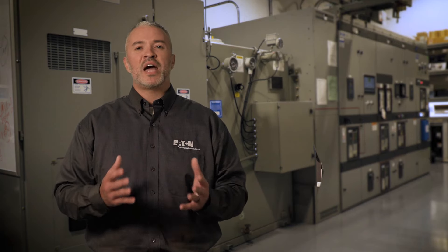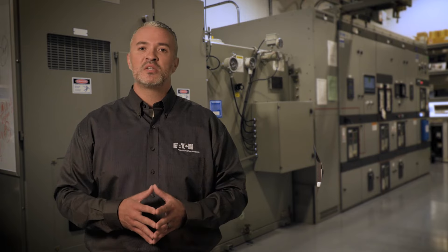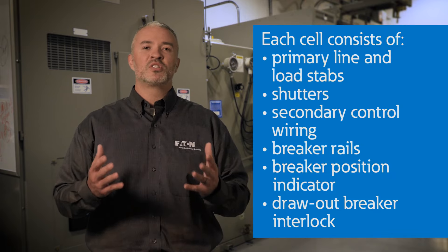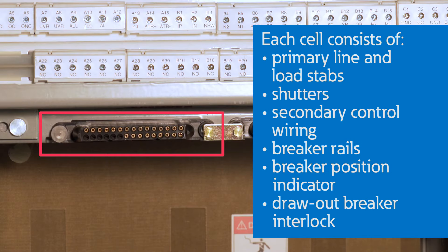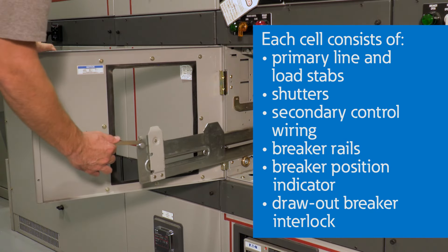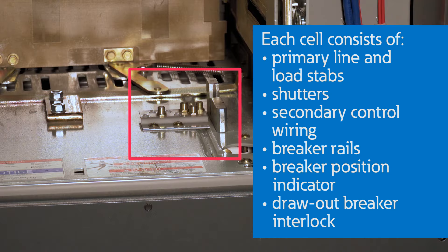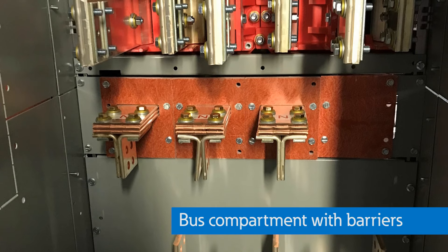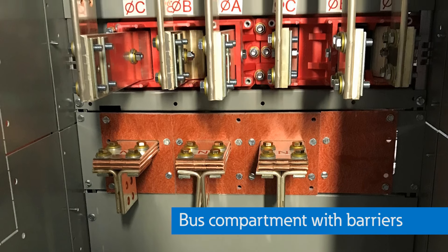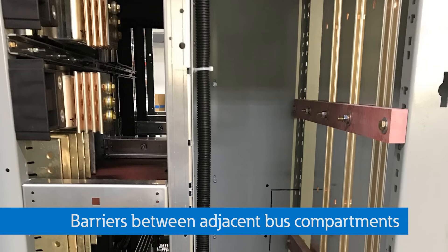For example, should a catastrophic fault occur on a circuit breaker, the internal barriers within the switchgear will reduce the likelihood of damage to adjacent breakers, internal bus, and the structure. Each compartment or cell generally consists of primary line and load stabs, shutters, secondary control wiring, breaker rails, breaker position indicator, and a draw-out breaker interlock which prevents the insertion of circuit breakers with incorrect frame size and interrupting ratings. Behind the circuit breaker compartment is the bus compartment, which is also compartmentalized by solid barriers from the breaker compartment. Adjacent bus compartments are segregated from each other by an insulated barrier between compartments.